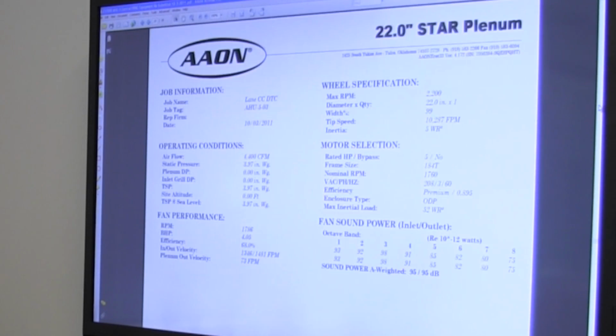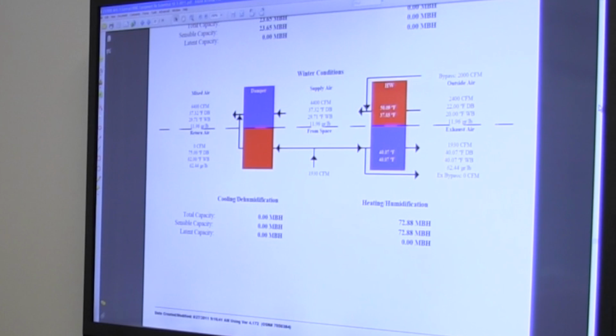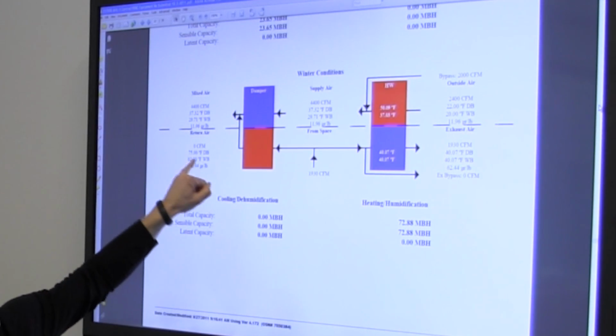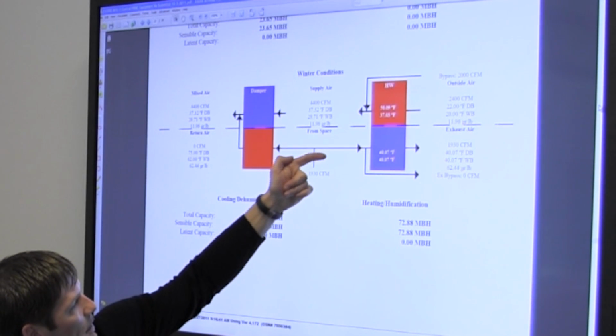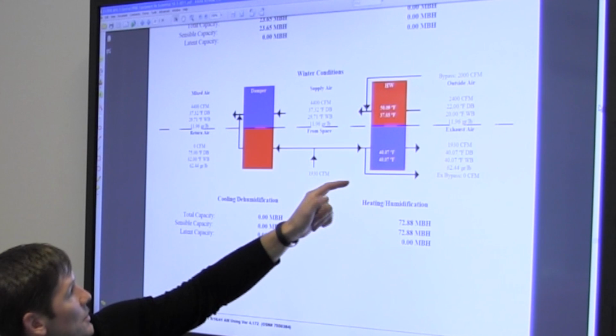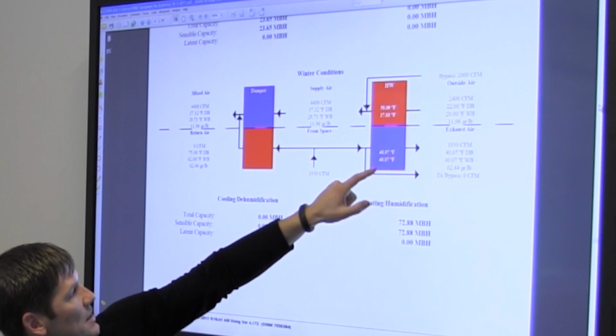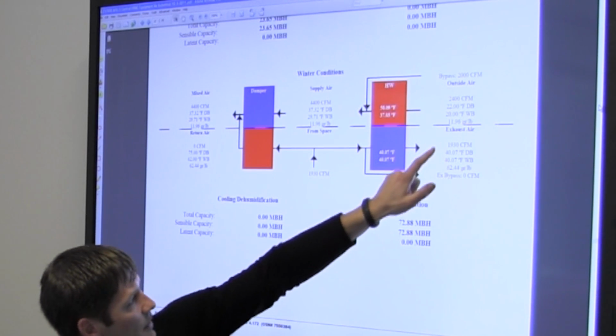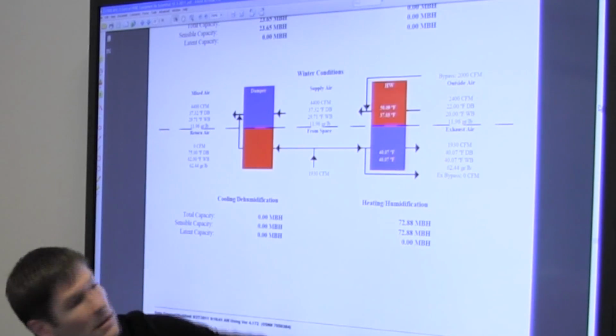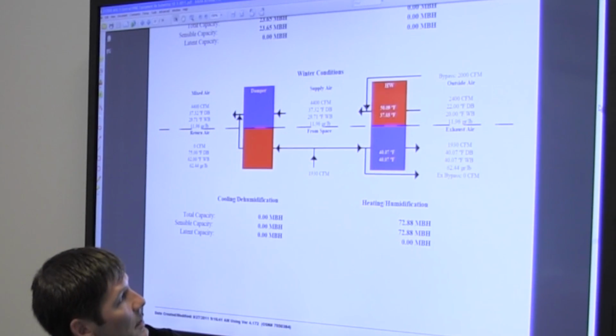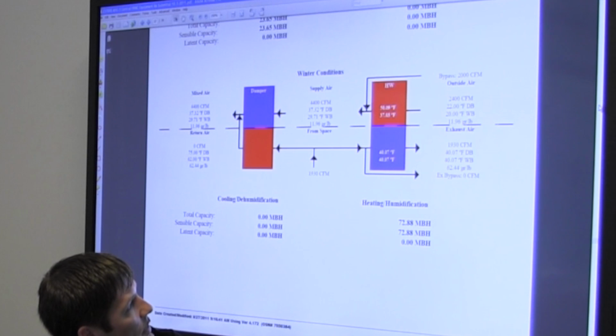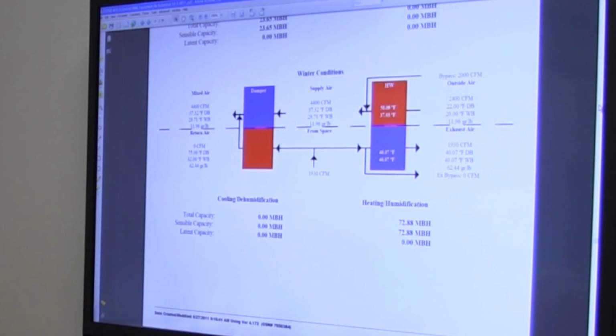Yeah, absolutely. We saw, what was it, 22 degrees up to, on the smaller unit, we're coming in at 75-degree return air. It cools that down to 40, so it just dropped 35 degrees out of the exhaust, and then it raises 22 degrees up to 50 degrees. So we're getting quite a bit of, 28-degree temperature rise. And that's on the smaller unit.